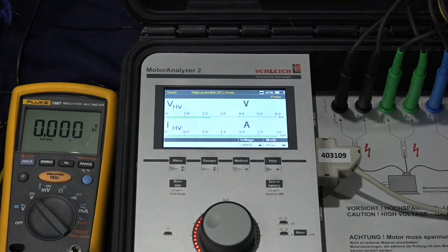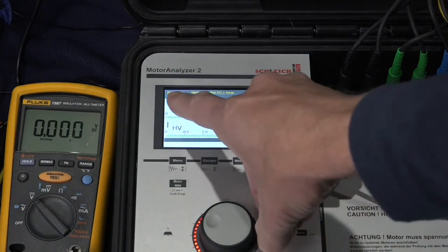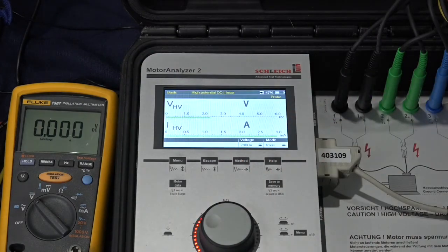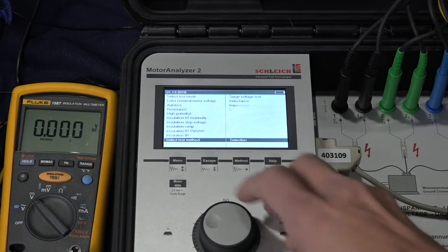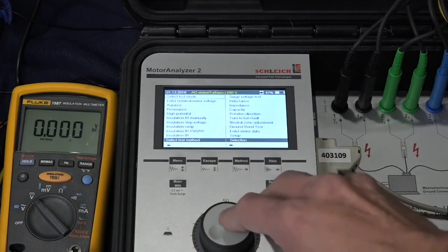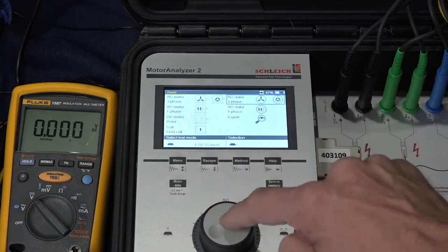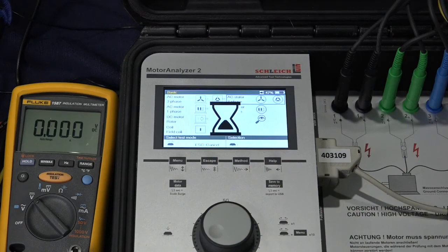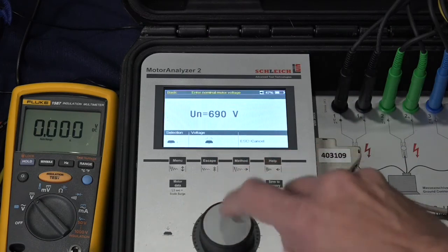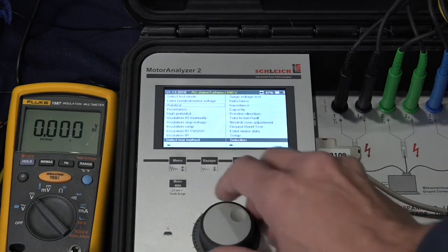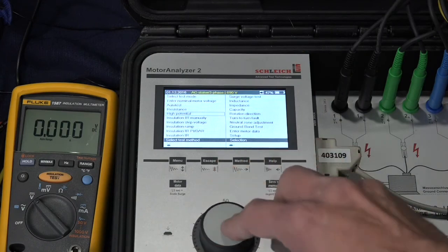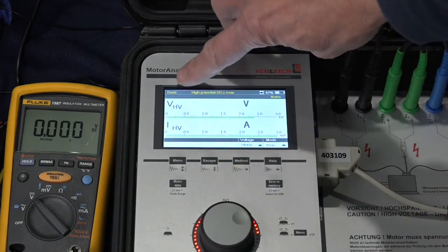So we've shown how to do a DC high pot test with the separate test leads, and we did that in what we call the basic mode of the tester. In the upper left-hand corner, you can see that we're in the basic mode. That comes from just coming up to our test mode, selecting a stator, entering a voltage here, and going down to the options we want to work with. You can see it's basic over there.